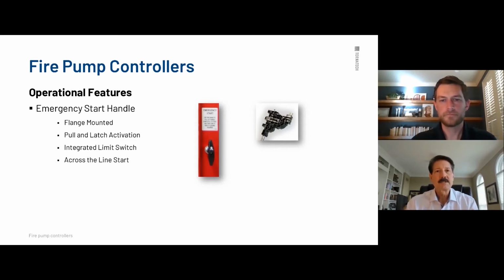Now, under emergency conditions, obviously that would be the perfect way to do it, but we understand if the building's burning and something's not functional and this is the only way, something else might happen. But again, when you're just doing your testing, follow that procedure because it's really the safest way. Plus, you don't have to worry about potential irreparable damage to the contactor or the surge or anything to the breaker from an arc that might occur. Yep, that's a good point. Thank you.